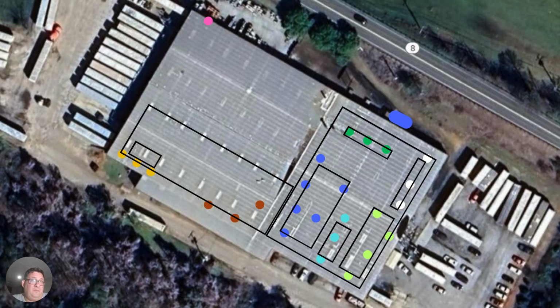And oh, by the way, one of the greatest ways to reduce your cost in a compressed air system is to isolate processes that don't need air when they're not being run. And when you use this design, it's a very easy way to shut one isolation valve, and now you've killed air to an entire section of a facility when it's not being run. In fact, this specific facility here, these three green dots had to run 24/7, but nothing else in the plant did.